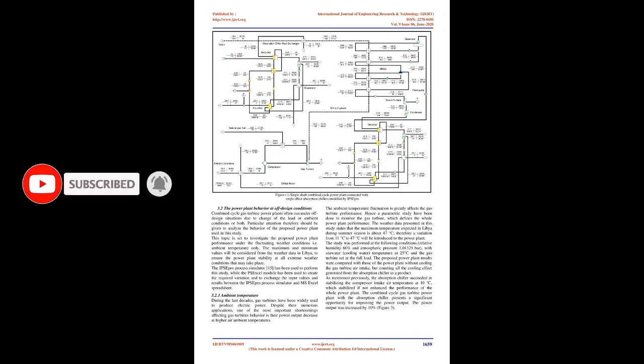7 showed that by utilizing the flue gas waste heat of the combined gas and steam turbine cycle power plant to power an absorption refrigeration system to cool the inlet air streams to 15 degrees Celsius in the gas turbine plants, an additional 51.1 MW of electricity was generated.